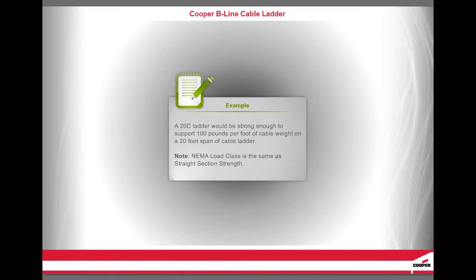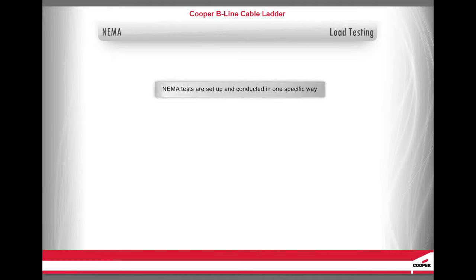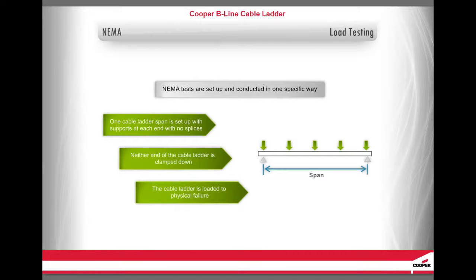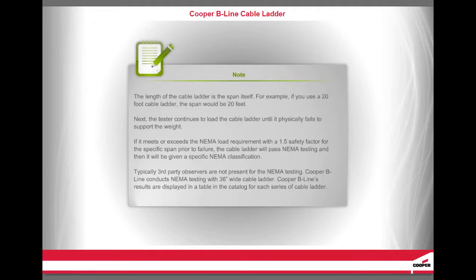Note: NEMA load class is the same as straight section strength. The NEMA tests are set up and conducted in one specific way. One cable ladder span is set up with supports at each end with no splices. Neither end of the cable ladder is clamped down. The cable ladder is loaded to physical failure. The length of the cable ladder is the span itself — for example, if you use a 20-foot cable ladder, the span would be 20 feet. The tester continues to load the cable ladder until it physically fails to support the weight. If it meets or exceeds the NEMA load requirement with a 1.5 safety factor for the specific span prior to failure, the cable ladder will pass NEMA testing and be given a specific NEMA classification.